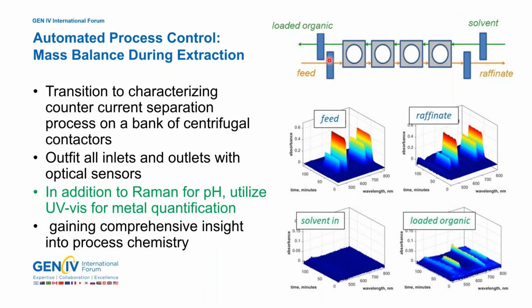The rectangles shown here in blue represent the locations on our bank of centrifugal contactors where we had UV-vis and Raman probes to measure in real time what went into the contactor in the feed, what came out in the raffinate, what went in as solvent, and what came out in the loaded organic phase. Down here are the spectra taken in real time by UV-vis for the feed location, raffinate, solvent in, and the loaded organic.